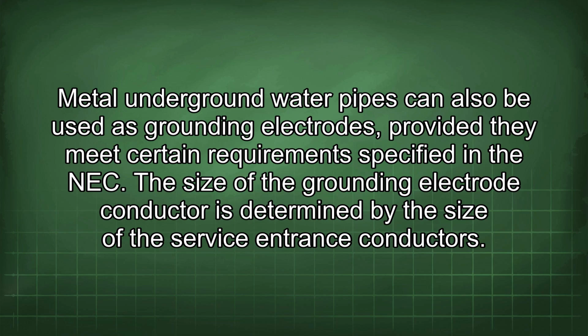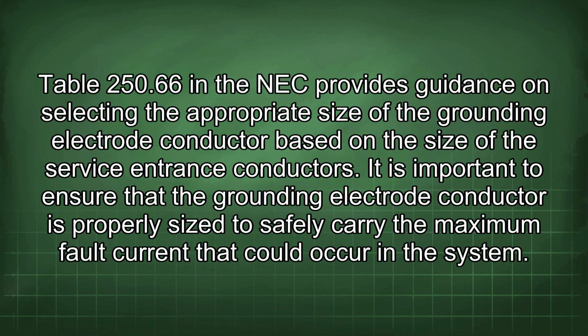The size of the grounding electrode conductor is determined by the size of the service entrance conductors. Table 250.66 in the NEC provides guidance on selecting the appropriate size of the grounding electrode conductor based on the size of the service entrance conductors. It is important to ensure that the grounding electrode conductor is properly sized to safely carry the maximum fault current that could occur in the system.